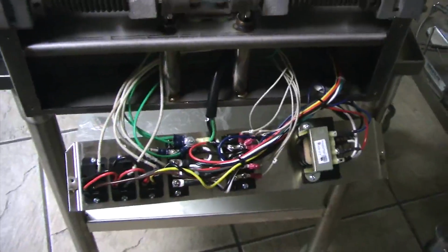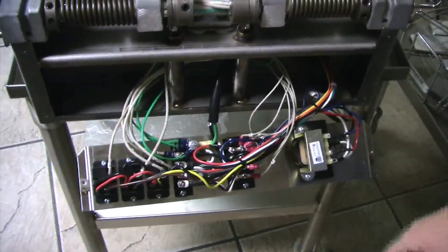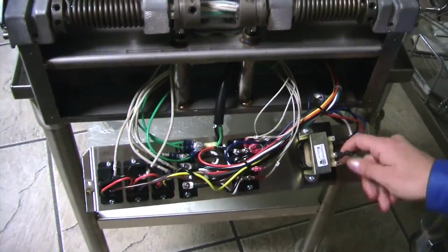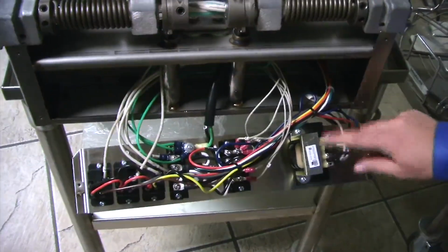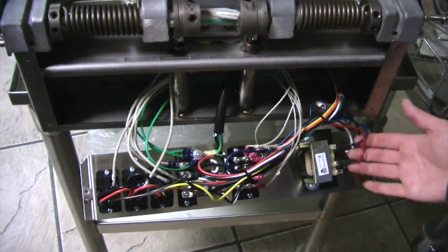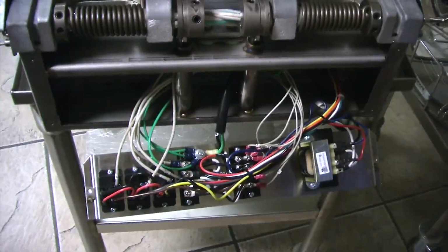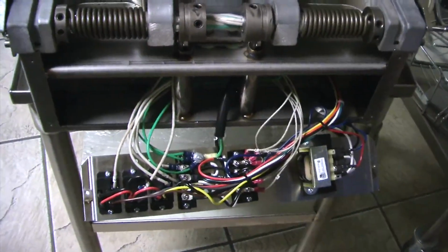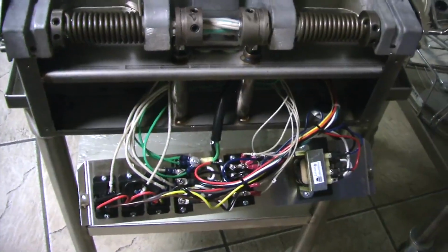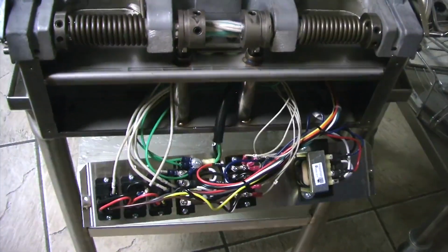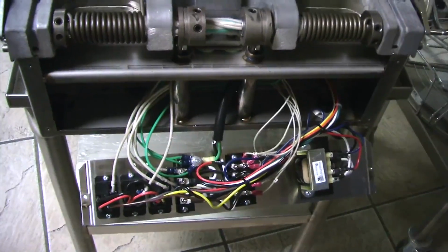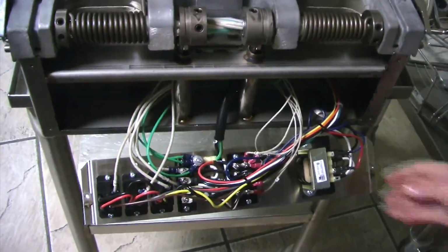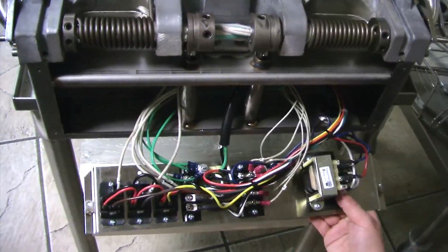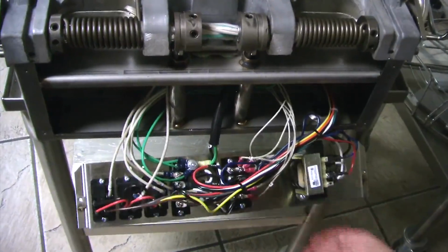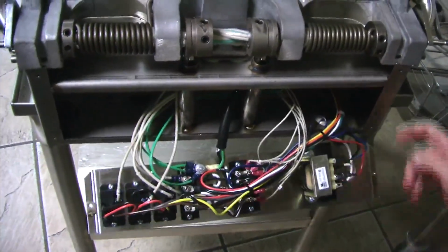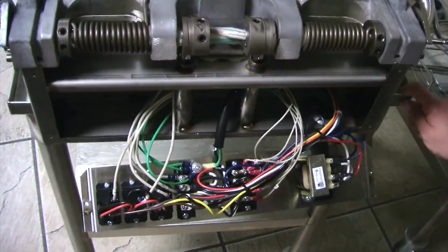Your transformer on your secondary side, check the voltages, and if you read 12 volts DC, that's going straight to your control board. So your control board's 12 volts DC. Here on your primary side, you're going to get 120 volts in if your machine's 120, and your 12 volt DC out. Your 12 volt DC will go straight to your control board.